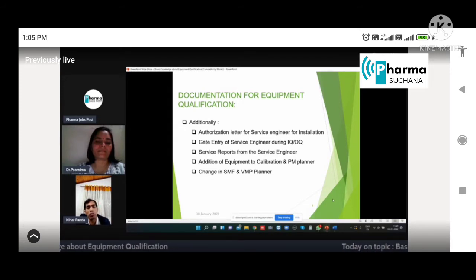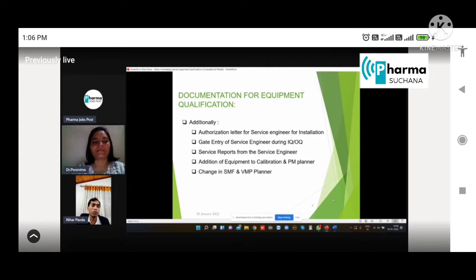Next is the service report. Whenever a service engineer comes, you should take a service report from them also. After installation, they have to provide a service report. After performance or operational qualification, they have to provide a service certificate or service report. Apart from that, after completion of the equipment qualification, you have to add this equipment to your equipment list. Even in the calibration planner, the PM preventive maintenance planner, your site master file, and your VMP, validation master plan, all these things need to be updated after completion of the PQ.